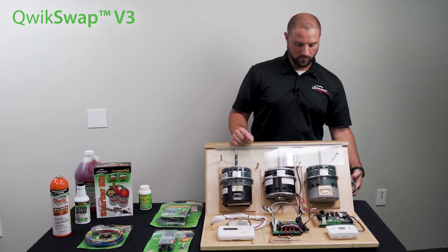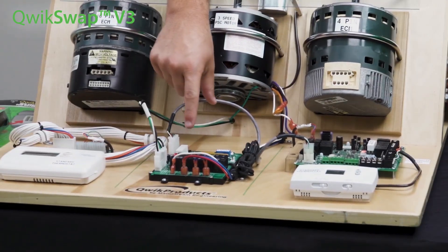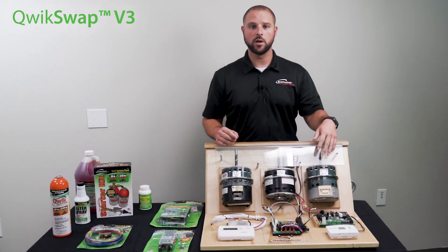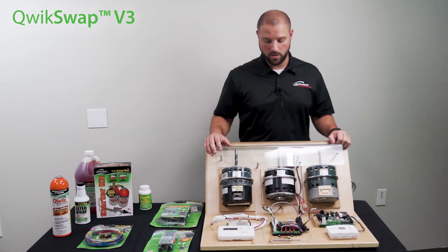So now we've left the OEM control board where it is. It now communicates with QwikSwap. And then the QwikSwap is now going to let the standard PSC motor run in place of the variable airflow motor, and it will actually allow it to change between high, medium, and low speeds during operation as well.